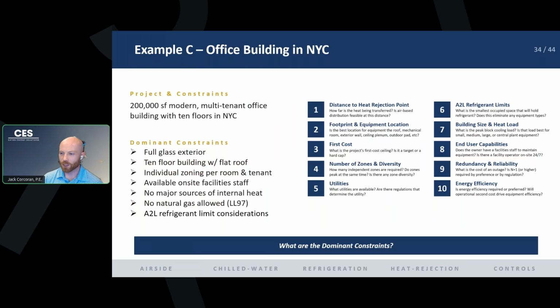We're going to have individual zoning again per room and per tenant. Maybe there are multiple tenants on different floors. And with this larger building, maybe the landlord has an on-site facility staff. Again, we're going to have no major sources of internal heat. There's no natural gas allowed here because of Local Law 97 in New York City. And we want to keep those A2L refrigerant limits down, right? We don't want to deal with A2L here. Maybe that's a client-driven request, but it is one of our dominant constraints in this project. Is this a good rooftop project?